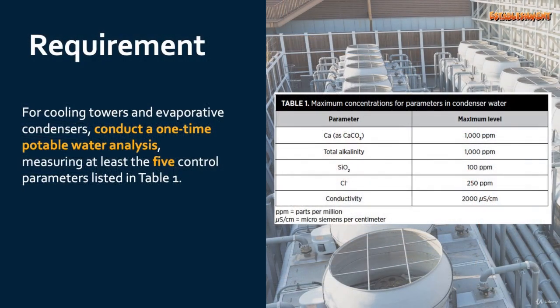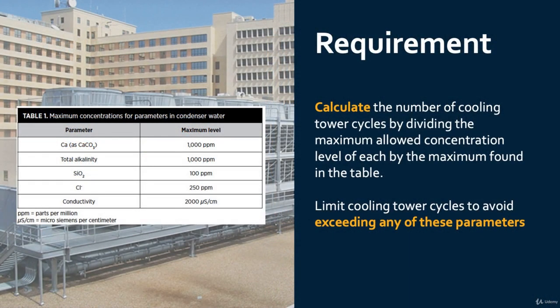The requirements are as follows. For cooling towers and evaporative condensers, conduct a one-time potable water analysis, measuring at least the 5 control parameters listed in Table 1. Then calculate the number of cooling tower cycles by dividing the maximum allowed concentration level of each by the maximum found in the table, and limit cooling tower cycles to avoid exceeding any of these parameters.